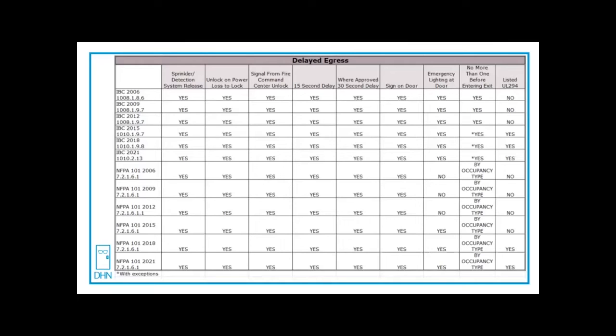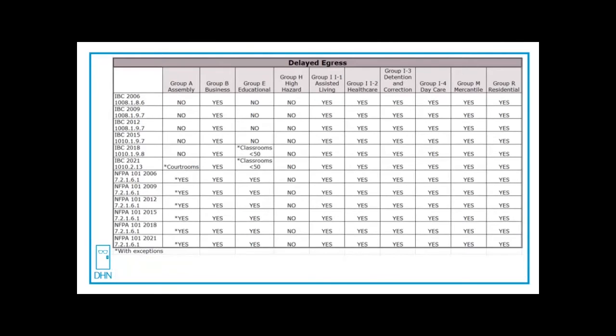UL 294 listing started in IBC 2015 edition and in NFPA 101, the 2018 edition. But you also have to look at which occupancy types will allow delayed egress. The next chart is comparing the different occupancy types.